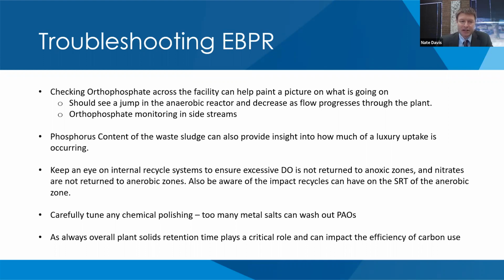Most facilities that we design for biological phosphorus removal, we do include provisions for chemical removal as well. They're necessary whenever you have hiccups in your influent or biology. The one thing to consider on that, though, is that feeding the chemical, especially depending on where you're feeding it, can erase the competitive advantage for the PAOs. So really carefully tune any chemical polishing that you're doing, and be aware that it is possible to wash your plant out with those. And again, solids retention time, similar to any other operations, plays a critical role in how these perform.